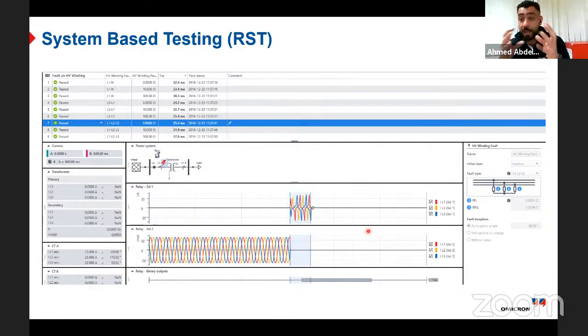Which one operates correctly? The one which tripped or the one which didn't trip? Then you need to calculate everything to ensure that maybe this one has a sensitivity issue, it doesn't trip, or maybe this one is oversensitive, so it trips. So you can avoid this confusion moment with pre-testing. Draw your system, simulate the same fault to both relays simultaneously, and expect the worst case scenario in your system. And finally, you can see and decide, yes, my system works fine.